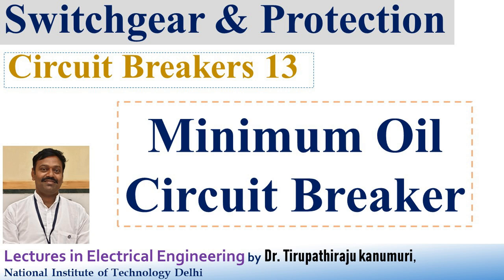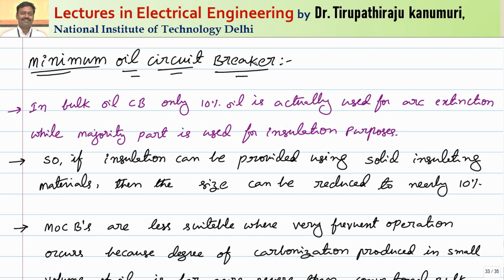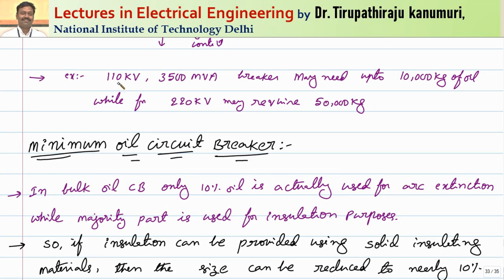Today we are going to discuss the minimum oil circuit breaker. In the last class we saw the bulk oil circuit breaker, where for a rating of 110 kV the breaker needs about 10,000 kgs of oil, which is very huge. Because of this huge quantity of oil, the size of the circuit breaker increases. Due to frequent operation, whenever contacts are opened, the oil decomposes into gases and carbon gets deposited on the contacts. To clean or check the contacts, we have to remove all the oil from the tank, which is very costly.